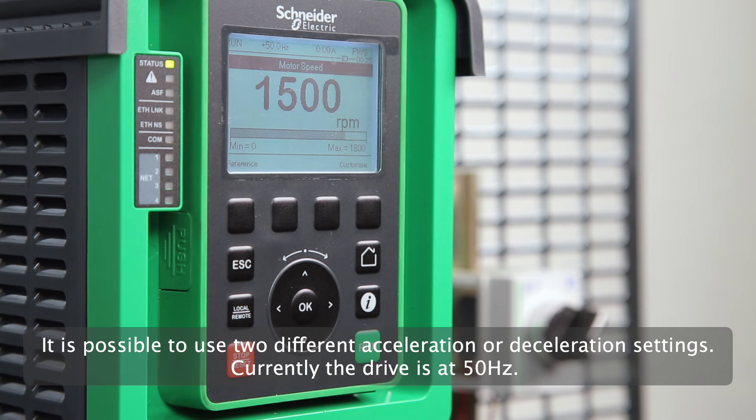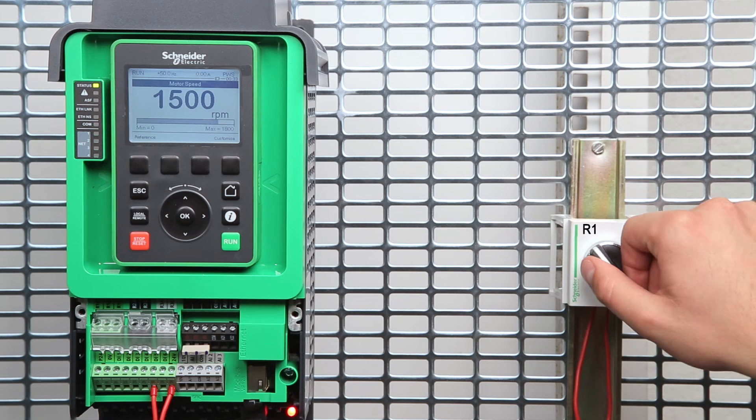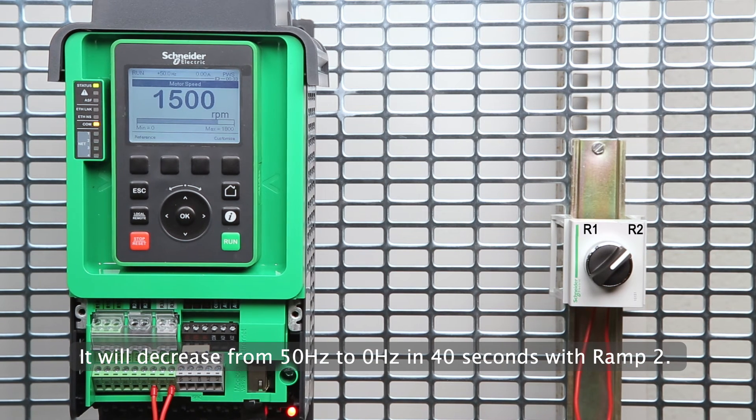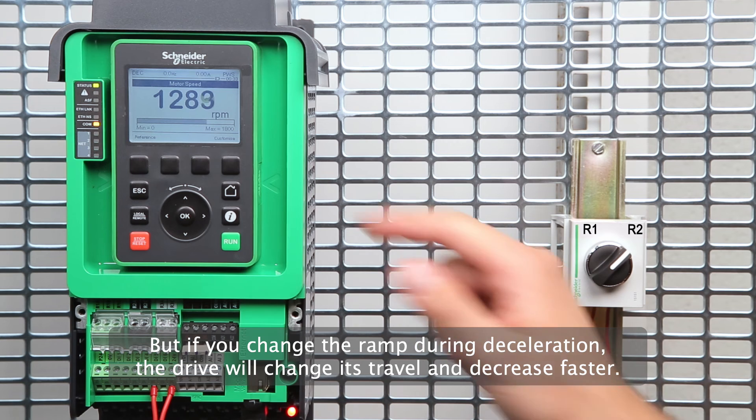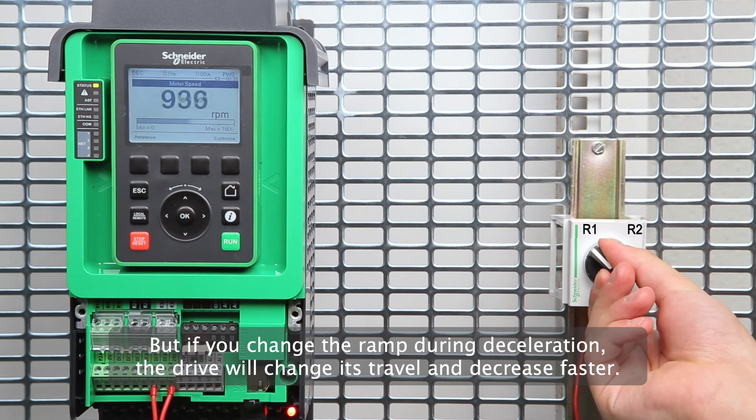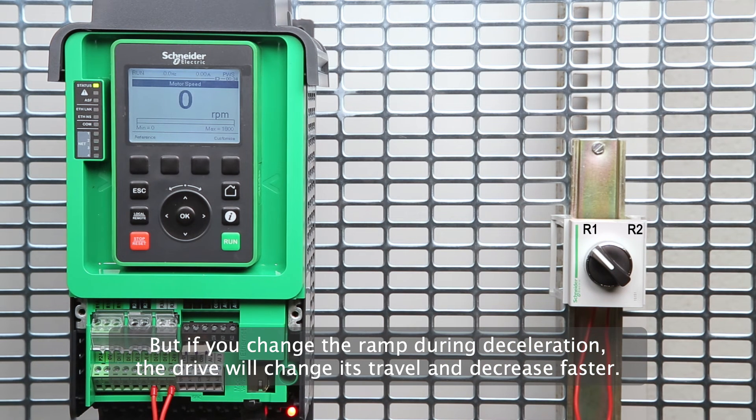It's possible to use two different acceleration or deceleration settings. Currently, the drive is at 50 hertz. It will decrease from 50 hertz to zero hertz in 40 seconds with ramp 2. But if you change the ramp during deceleration, the drive will change its travel and decrease faster.